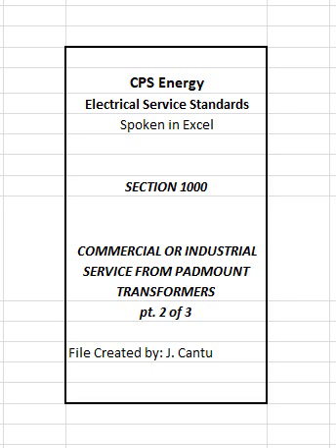3. Where the subsoil conditions are questionable, CPS Energy shall require the customer to provide a Proctor density test at their expense to determine if the slab shall be built on piers. A 90% Proctor test is necessary to eliminate the need for piers. 4. Customer shall furnish and install 2 5/8-inch x 8-foot copper or copper-clad ground rods in the slab, as specified in CPS Energy slab detail. CPS Energy will provide and install all necessary ground rod connectors.